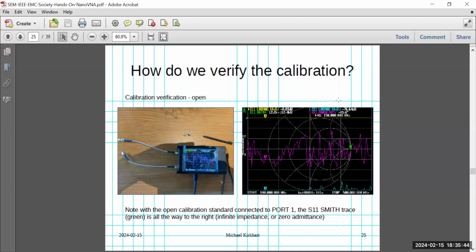So now to verify the calibration, if you've got the two connected together, remove the connection and put the open back on. Then, if you've got S11 — which I think these default to having as trace 3, S11 Smith — look at the Smith chart and you should see a dot on the right side of the chart. Is everybody seeing that? You're probably already seeing something close to that without the open standard connected, because it's kind of already open.